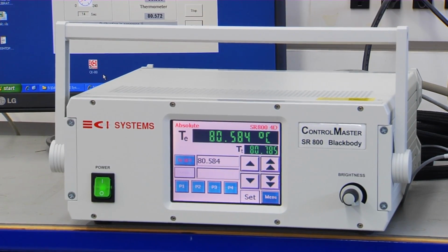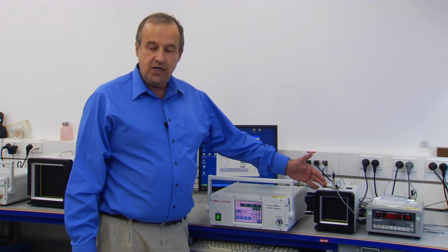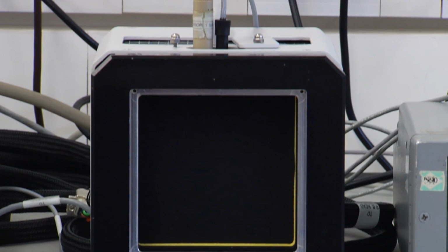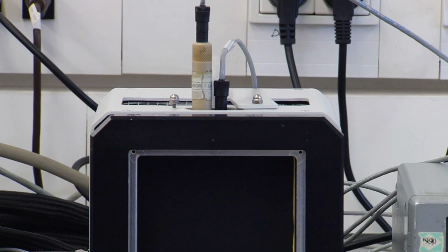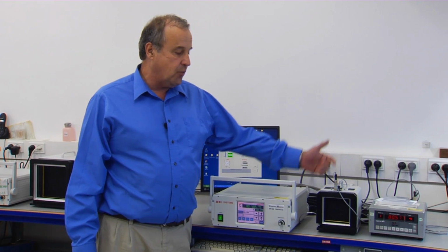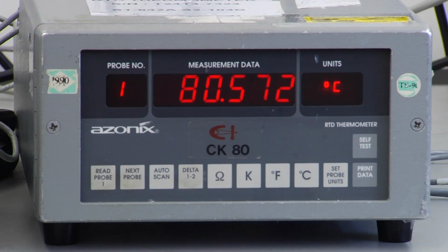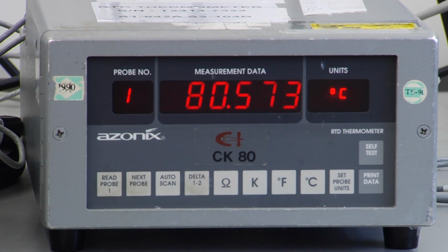Here we are calibrating CI Systems blackbodies, which are built of a controller and a radiation head. The calibration is performed by a master sensor connected to a very accurate thermometer, running the calibration automatically.